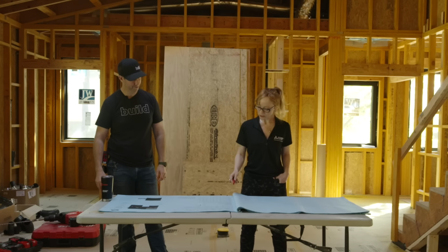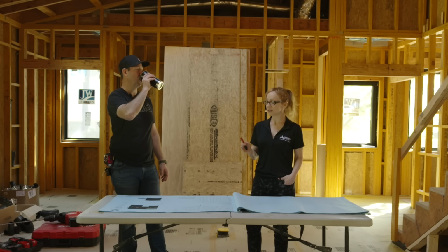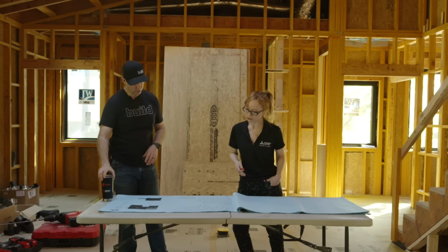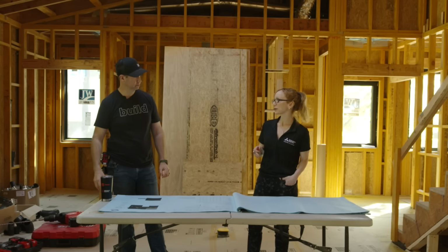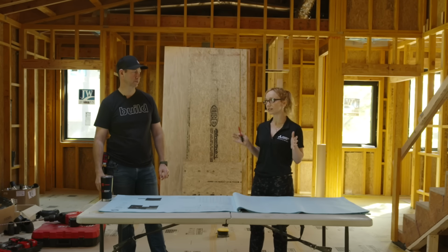Please do. So you had mentioned just how low load your home is, and it really is. How large is this house total? About 2,800 square feet. 2,800 square feet. So we're well over 1,000 square feet per ton in terms of space cooling. So we consider that low load.